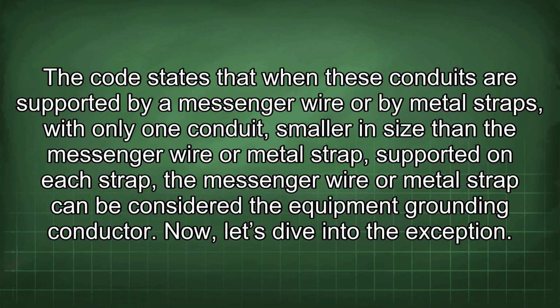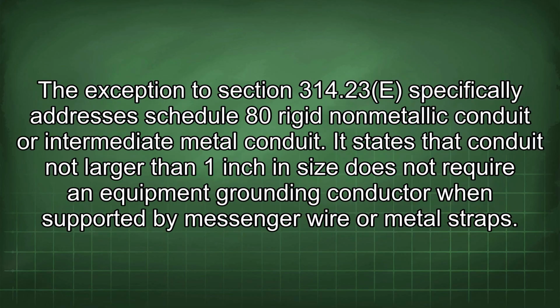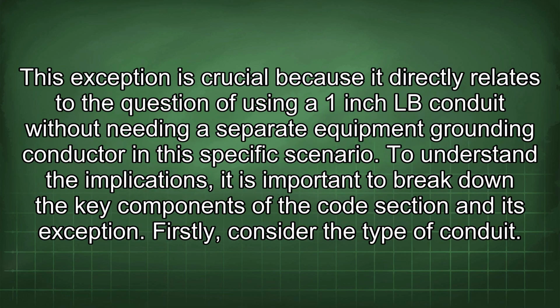Now let's dive into the exception. The exception to Section 314.23(E) specifically addresses Schedule 80 rigid non-metallic conduit or intermediate metal conduit. It states that conduit not larger than 1 inch in size does not require an equipment grounding conductor when supported by messenger wire or metal straps. This exception is crucial because it directly relates to the question of using a 1-inch LB conduit without needing a separate equipment grounding conductor in this specific scenario.